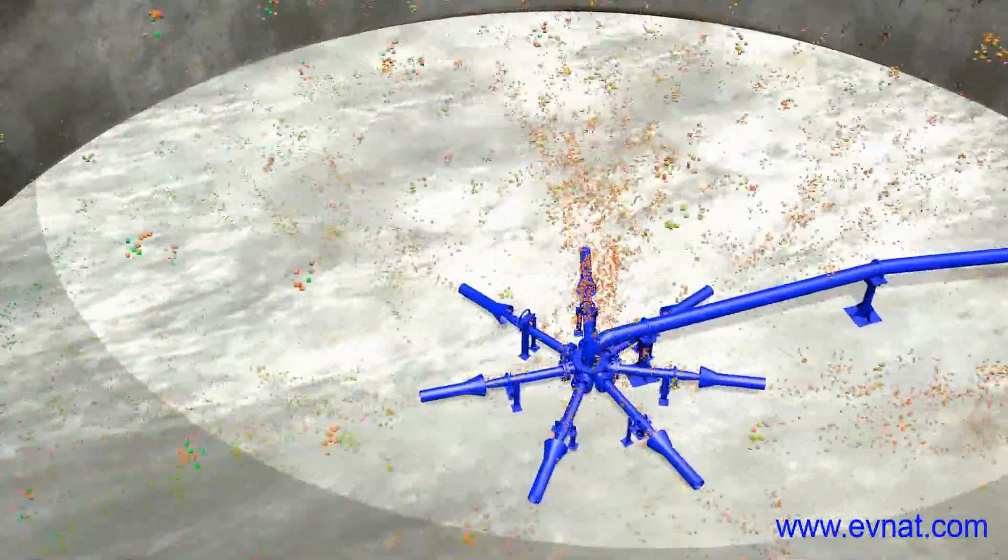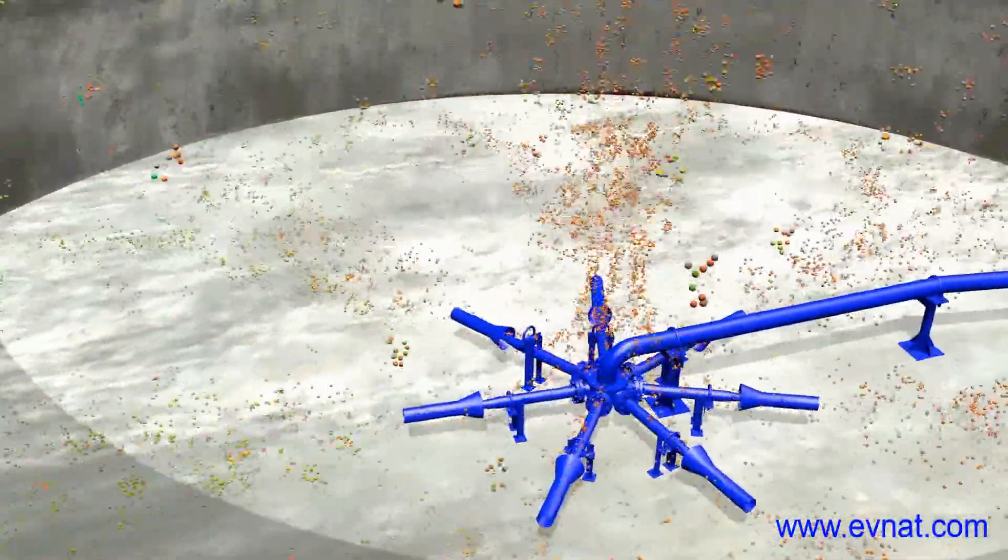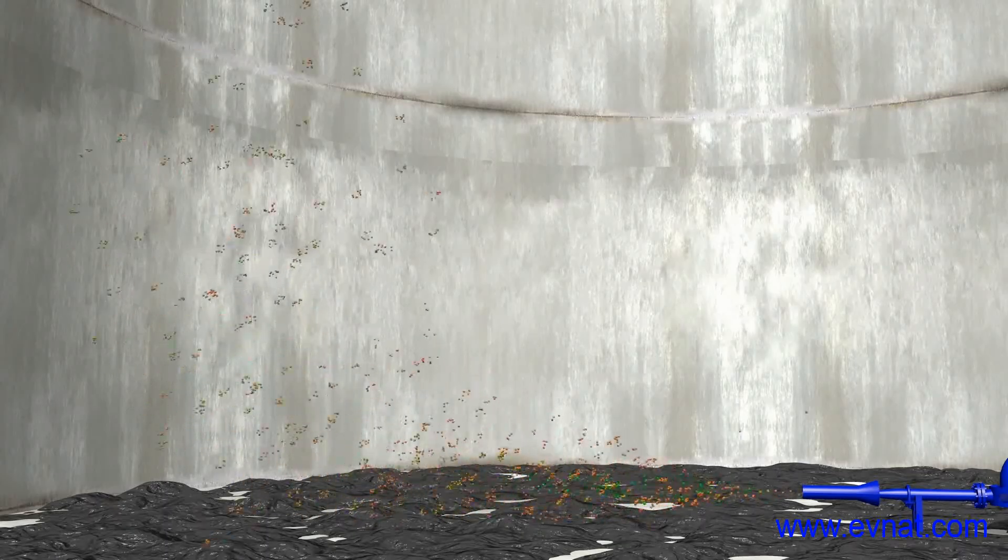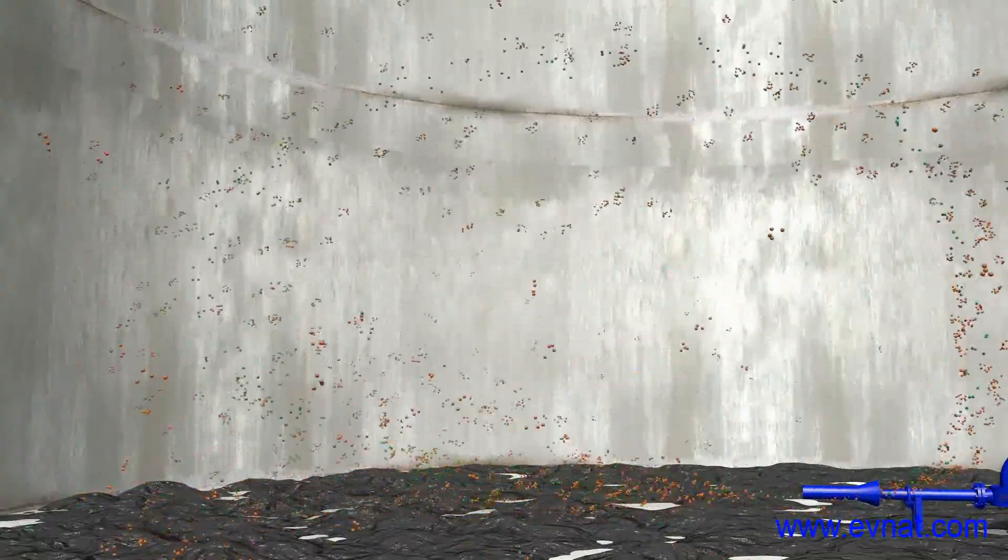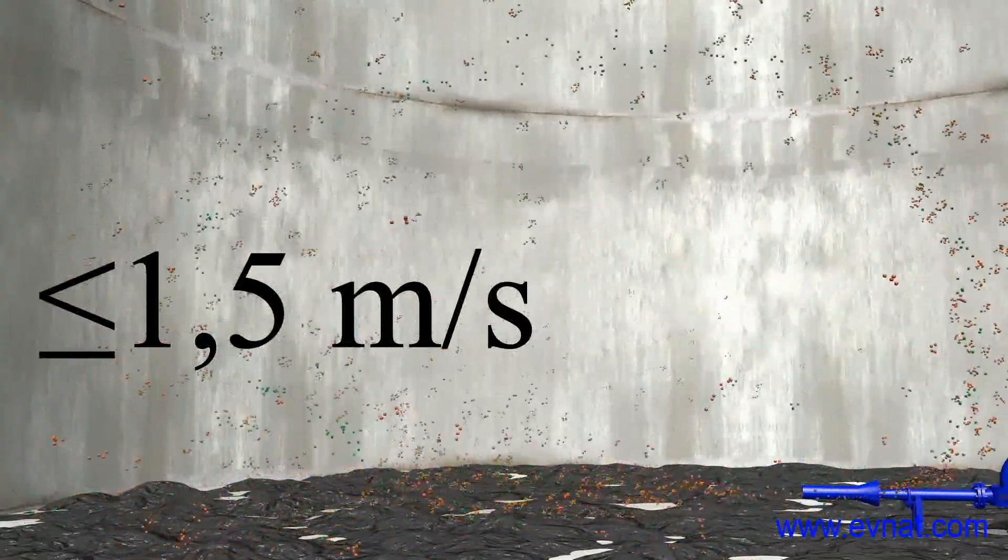The outlet flow speed is sufficient for tearing the precipitated oil sludge particles off the bottom and bringing them into a suspended condition. The jet speed at the tank wall must not exceed 1.5 meters per second.